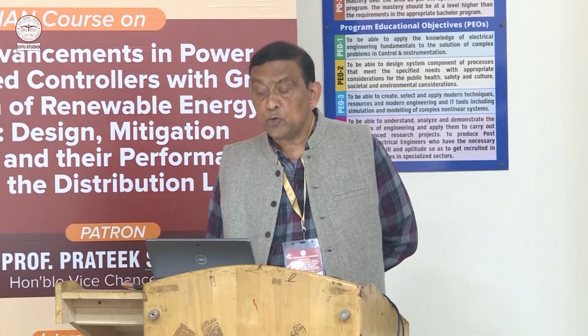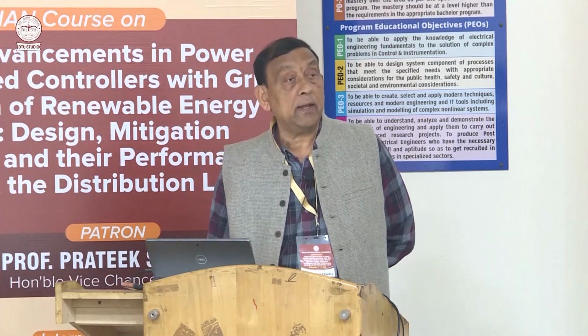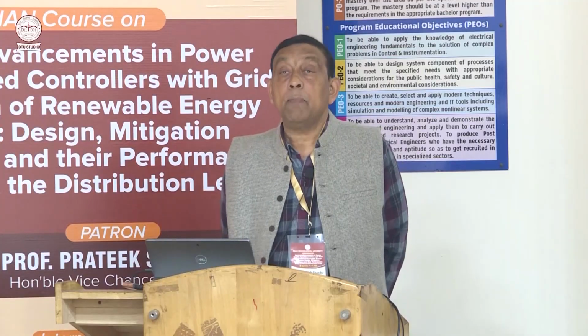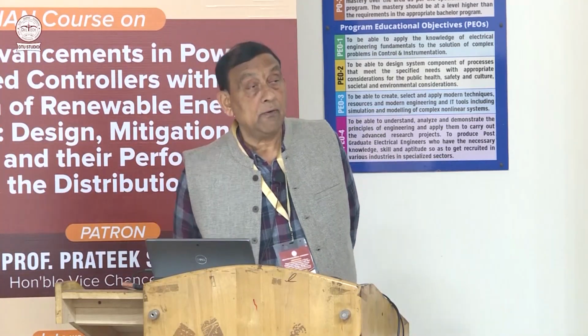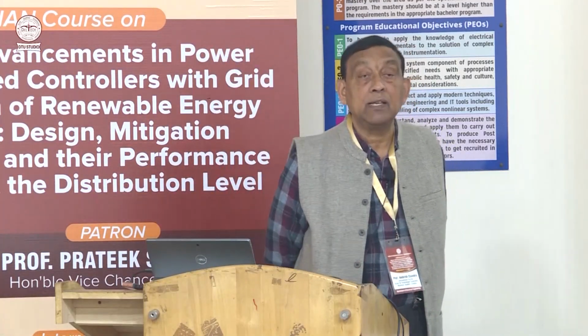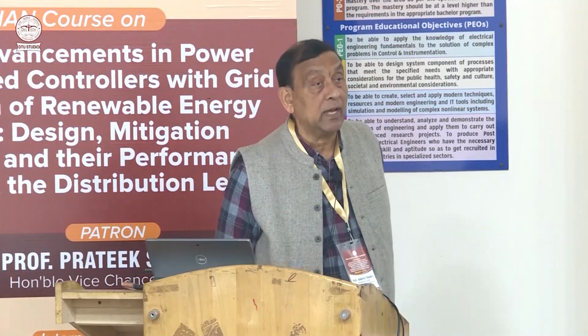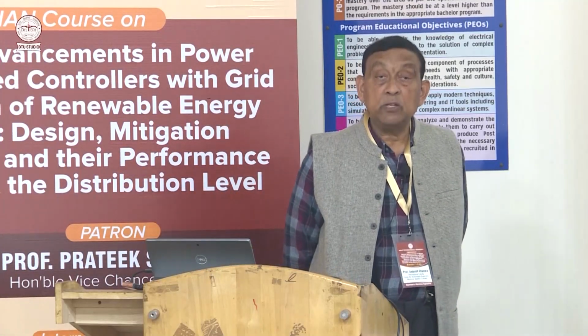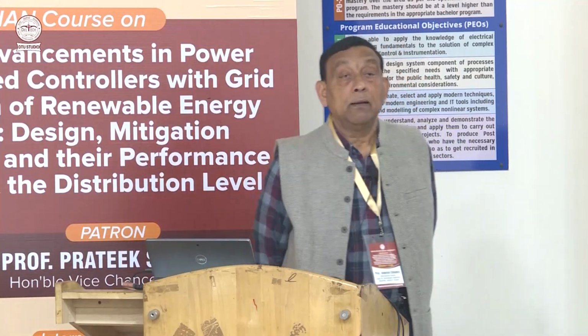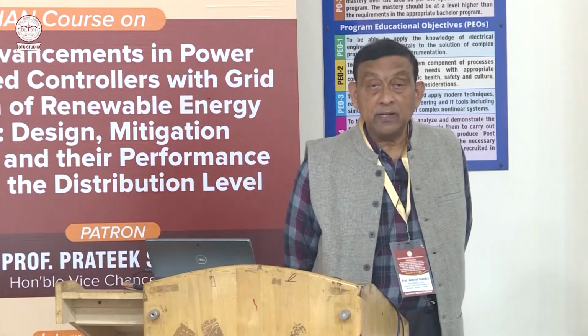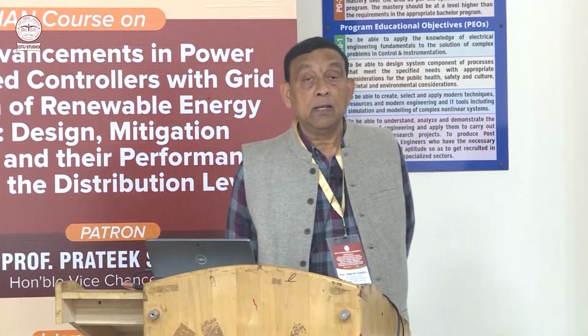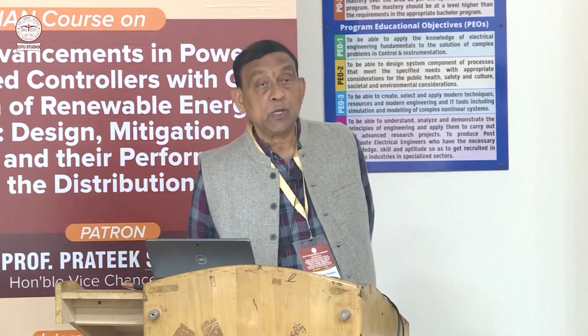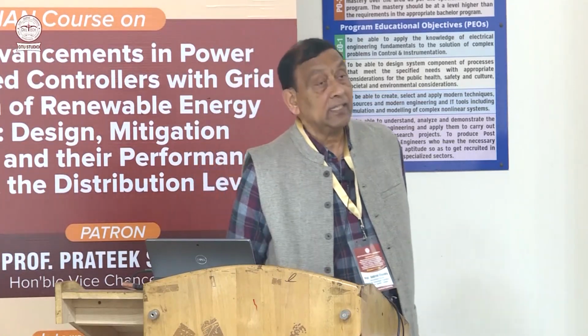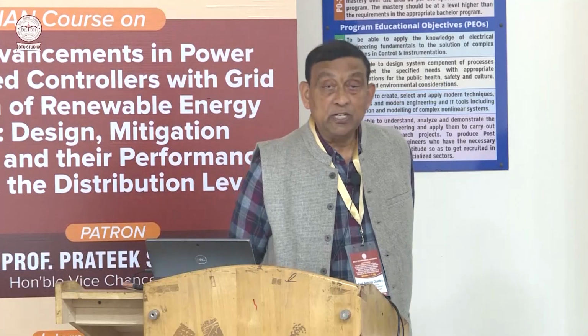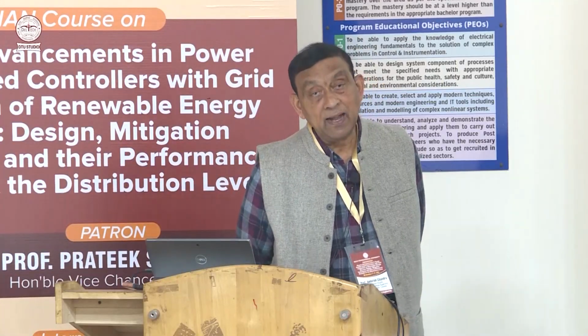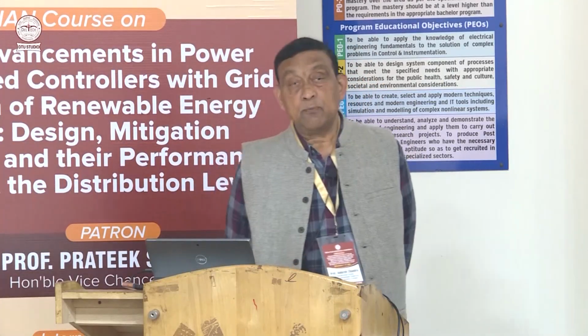And then large neutral current, of course. We know that in a normal balanced system, if we have IA, IB, IC, the sum will be 0 because of Kirchhoff's current law, because they are 120 degrees apart, right, phase shifting. But if you have the zero sequence current, then they are in the same phase. So instead of cancelling each other, they will add up. So that's why the neutral current problem may be there.